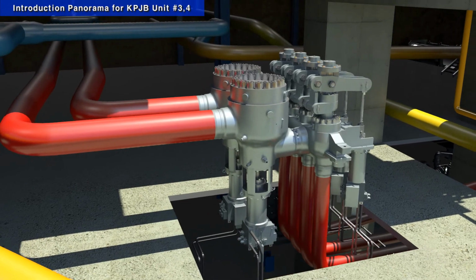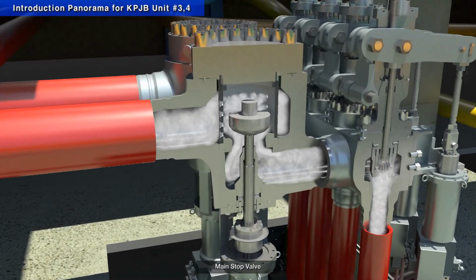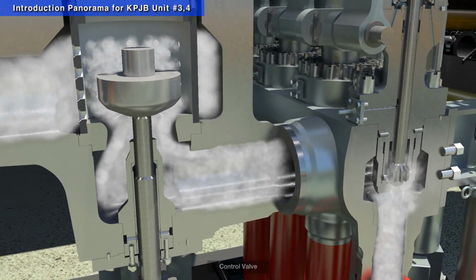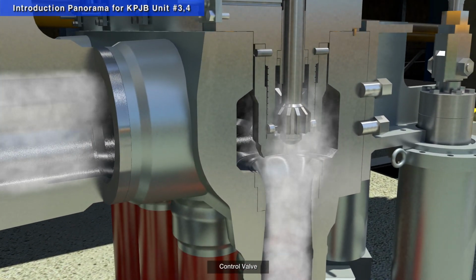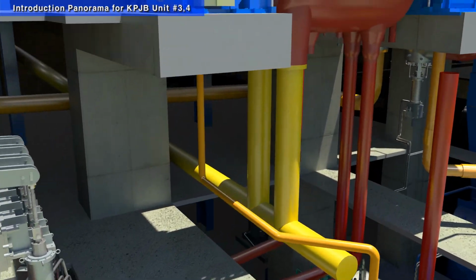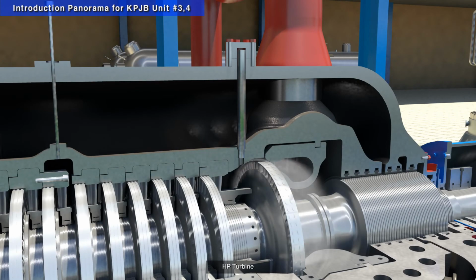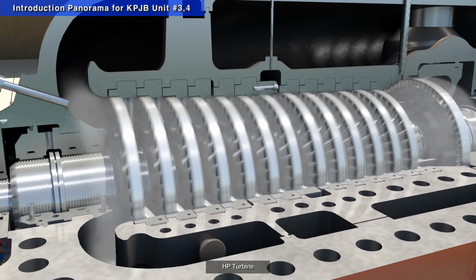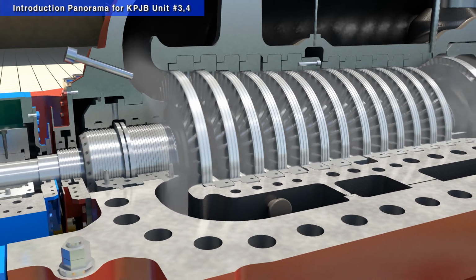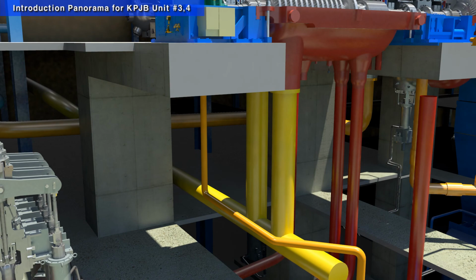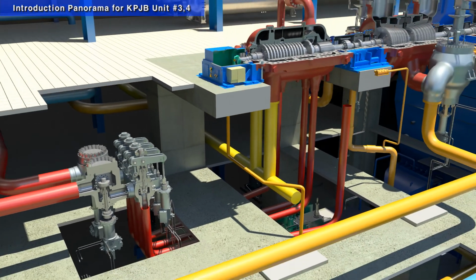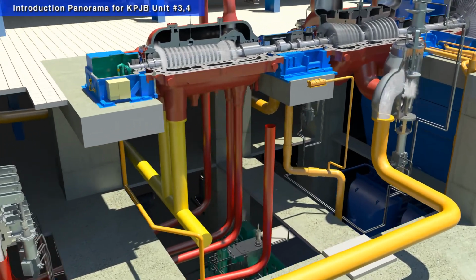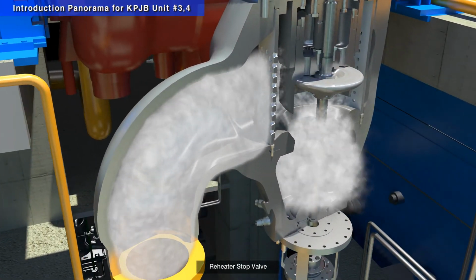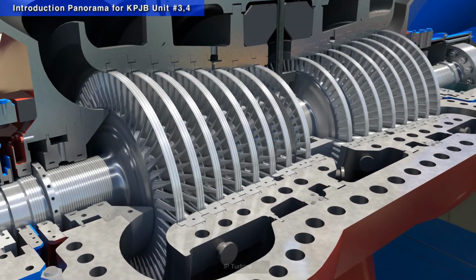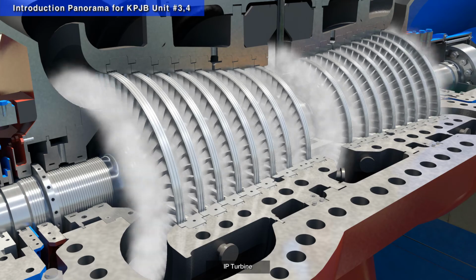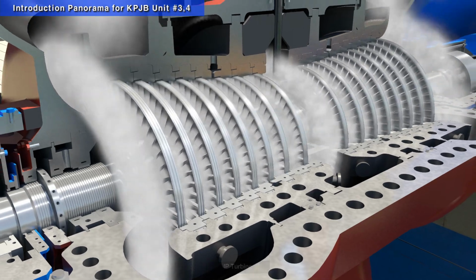The high-pressure superheated steam goes through the main stop valve and control valve into the HP turbine and goes into the reheater after extracting its energy from a fluid flow into useful work through 14 HP stages. The steam which has been reheated in the reheater goes through the reheater's stop valve and the intercept valve into the IP turbine. After it goes through 16 IP stages and passes the single crossover pipe, half goes into the LP turbine A and the other half into the LP turbine B and is condensed in the condenser after going through 24 LP stages.